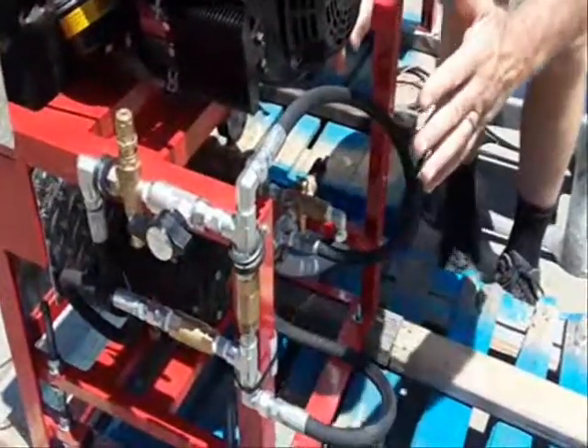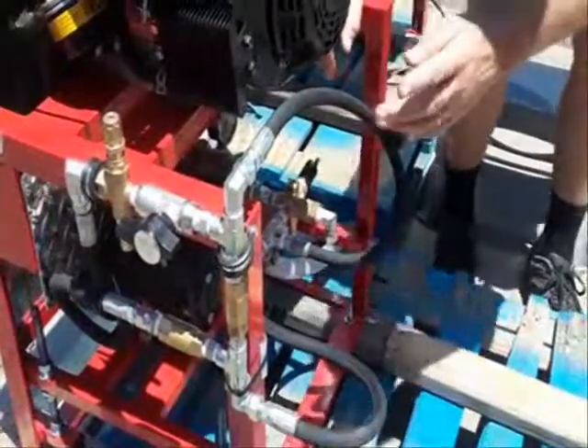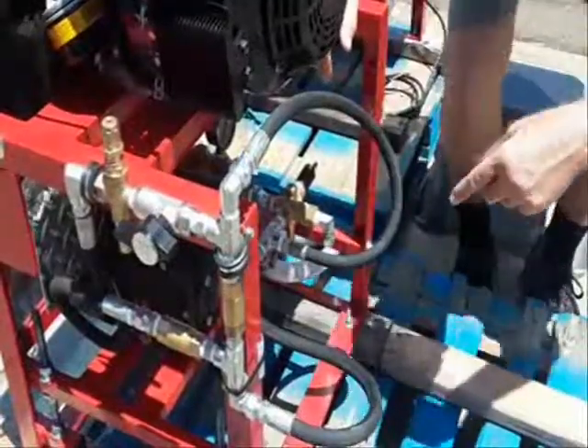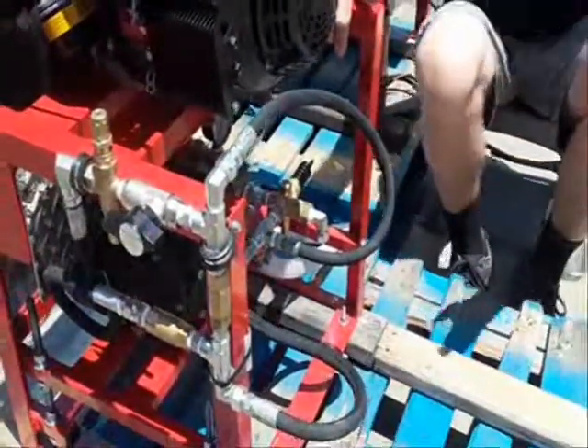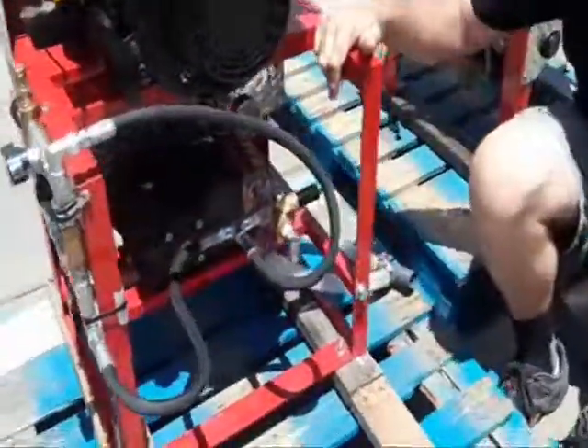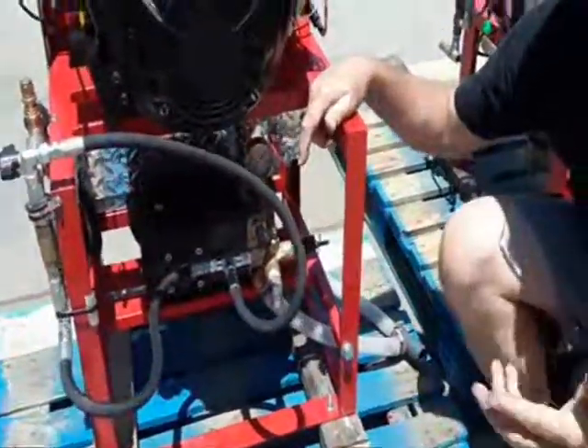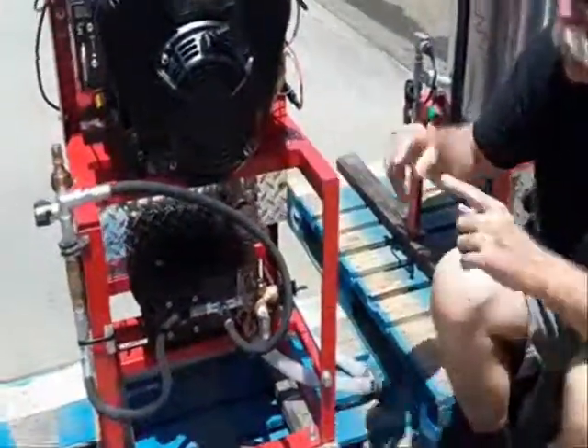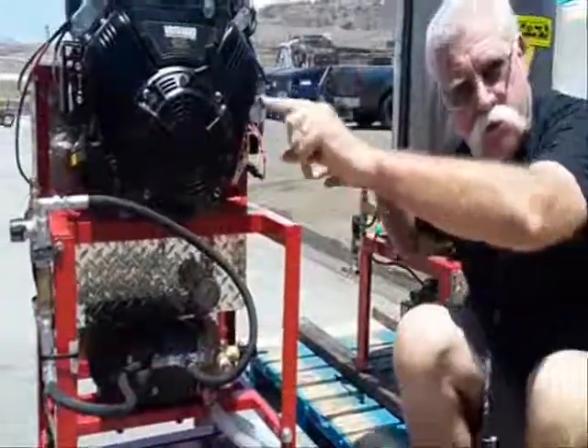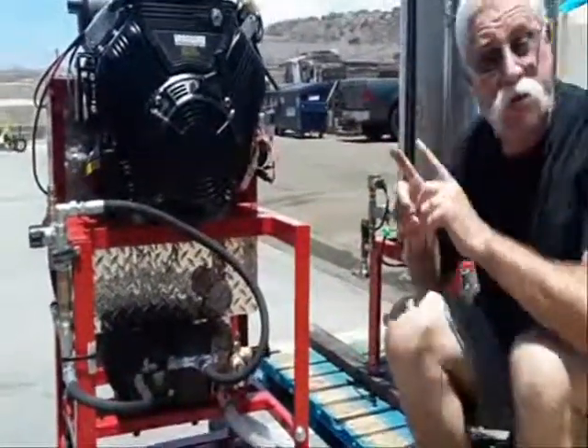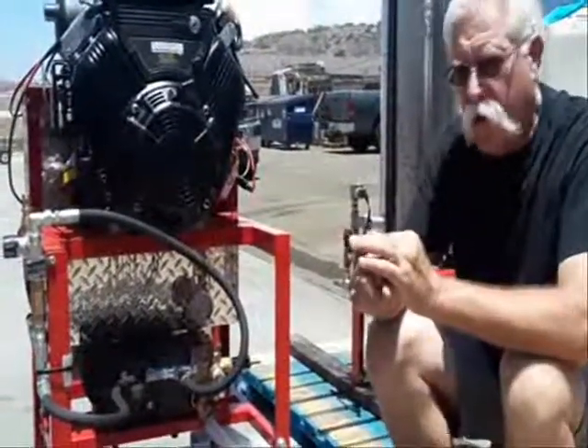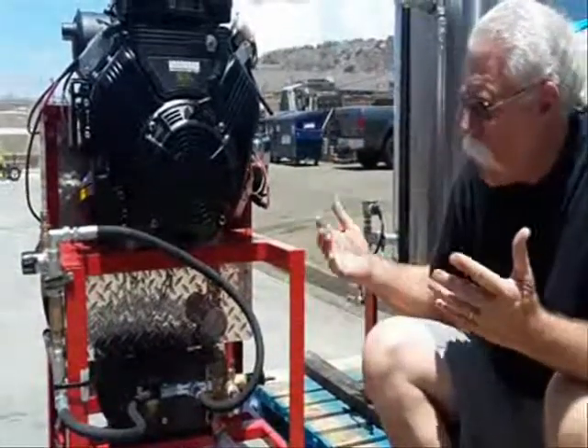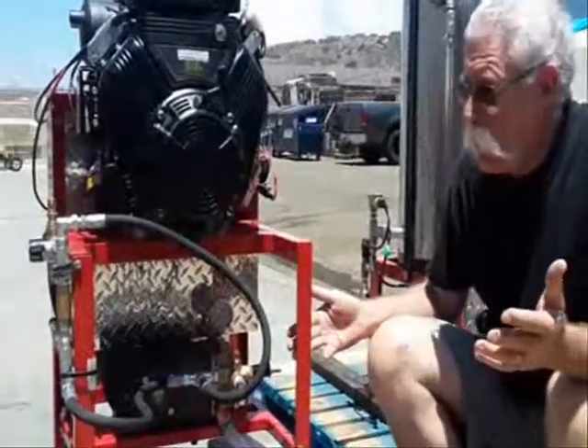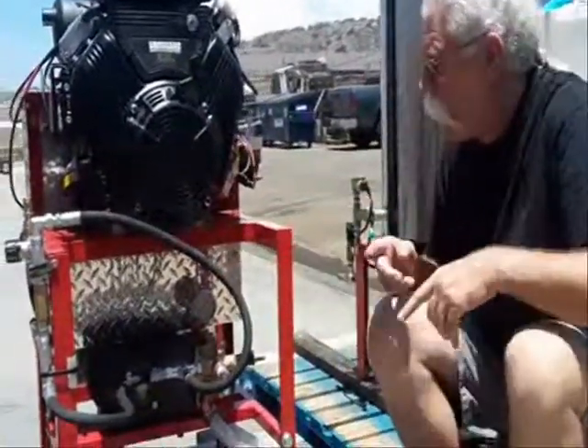Now let's talk about bypass lines real quick. If one of these is bleeding and it's not supposed to be bleeding, in order to troubleshoot this thing, I'm going to ask you which one of them is bypassing back to the holding tank. Your return lines back to your tank should be separate. We don't want to run them together, because if we're troubleshooting to figure out why it's not making pressure today, we want to know if that one's bleeding or if this one's bleeding.